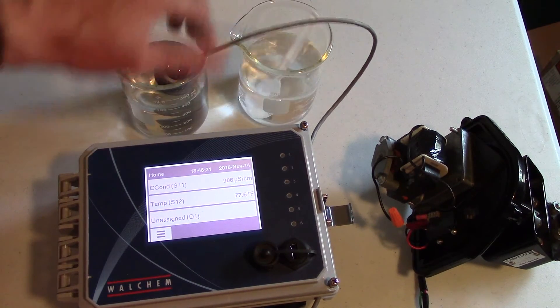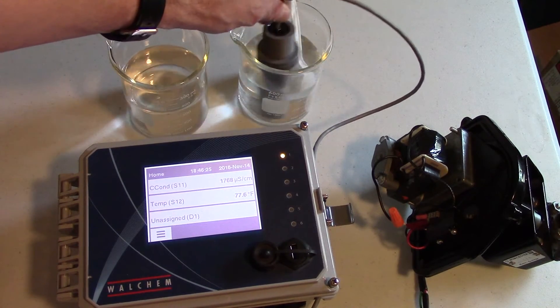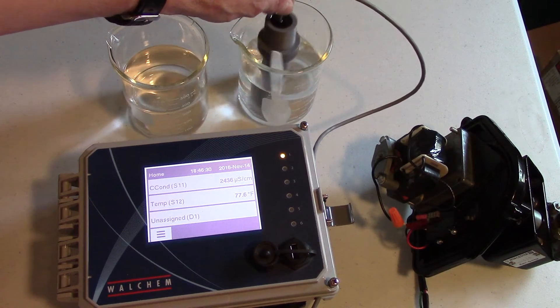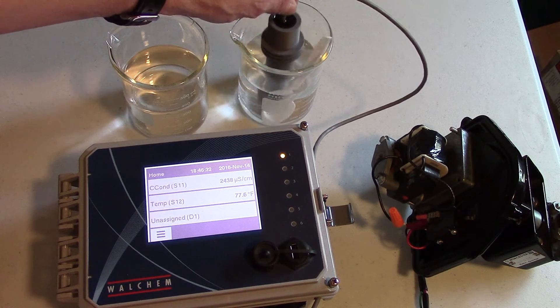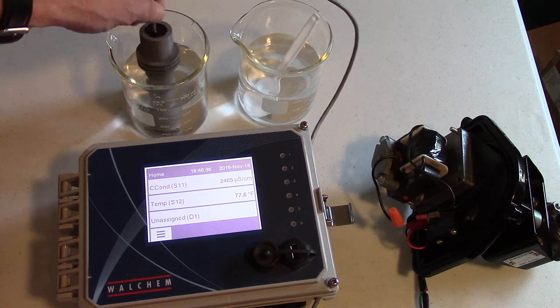I'll put it in the higher conductivity water and the valve should open up and it will stay open until it gets below the set point minus the dead band or below 1200, which of course it will.